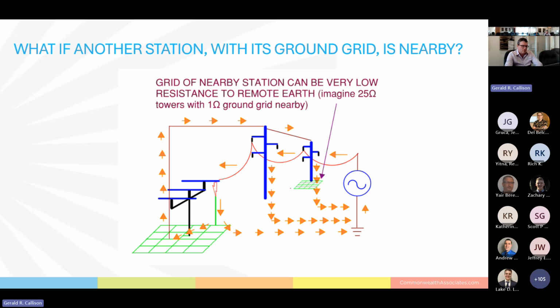So this is a picture of split factor with a neighboring ground grid nearby. I talked about how a typical very low value for grounding for transmission towers might be 15 to 25 ohms. Well, if you have a couple of spans of towers and then the shield wire enters a 1 ohm ground grid, like we see right here, that can have a very significant impact on split factor as well. So the proximity of nearby ground grids is another significant factor that impacts split factor. So with that, hopefully I have given you enough information that you can appreciate some of the very significant ideas that my colleague Rich Keil is going to be presenting to us.